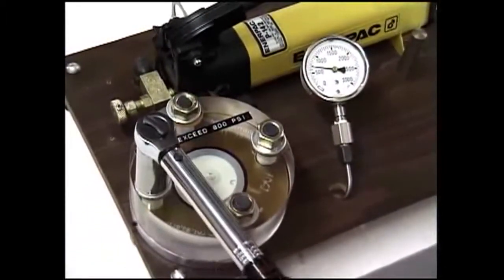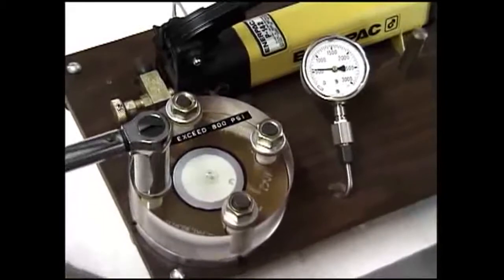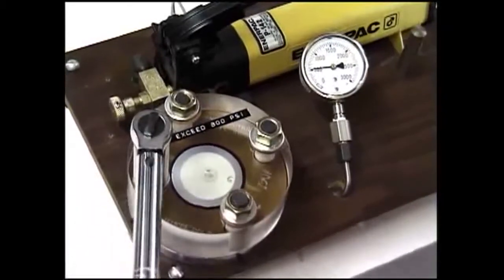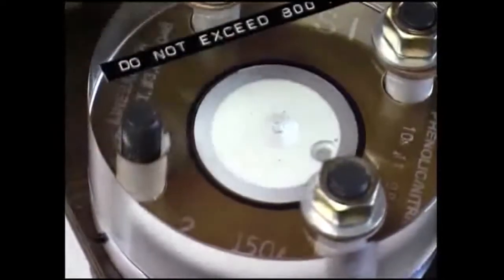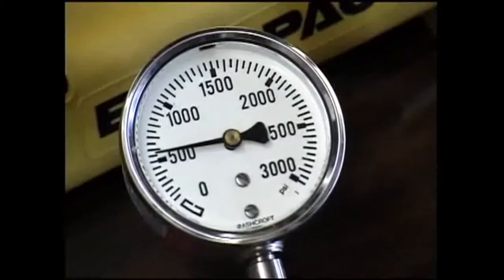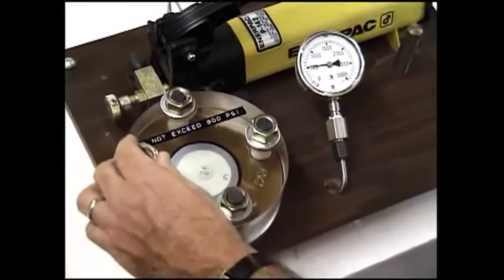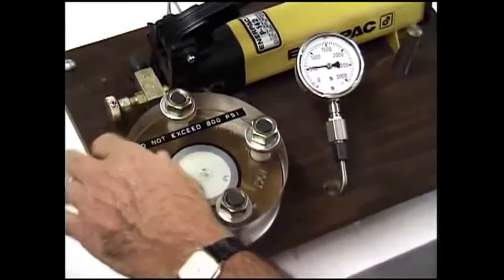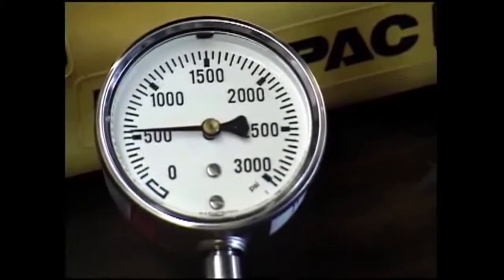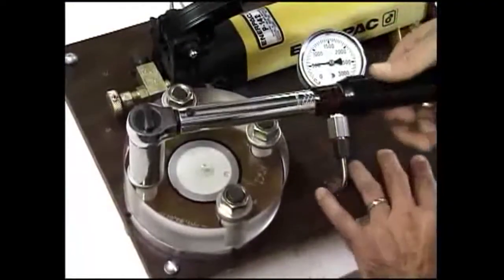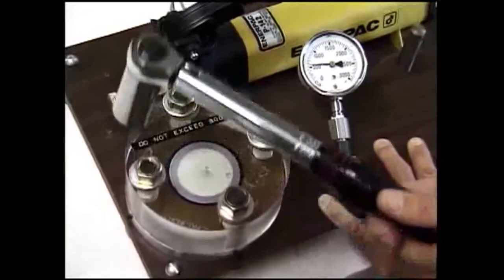To demonstrate more graphically the effectiveness of the linebacker sealing gasket, we'll remove one of the four nuts. Watch the pressure drop slightly due to increased internal volume between the gasket and clear platen. More importantly, you'll note there is still no leakage across the gasket face. In fact, we can re-tighten the nut and the pressure will increase as the seal was actually never broken, even with one nut removed.